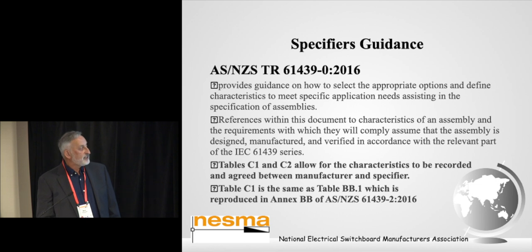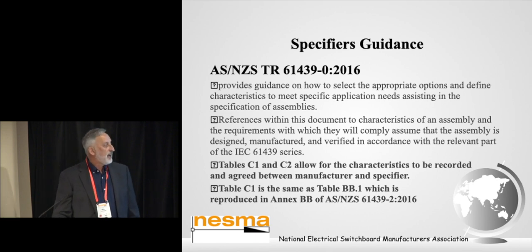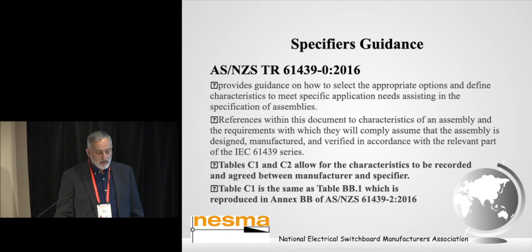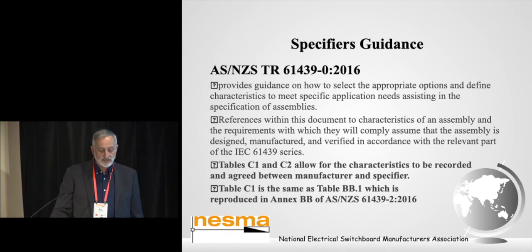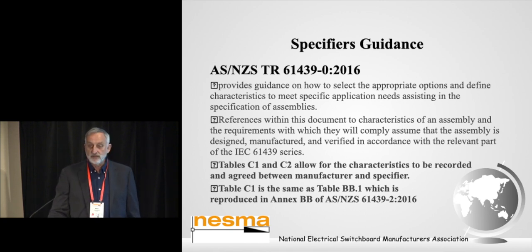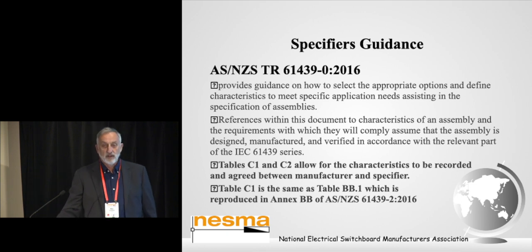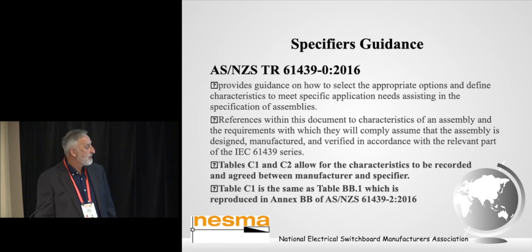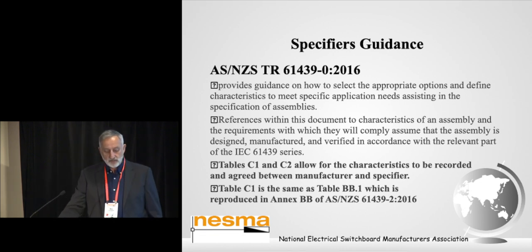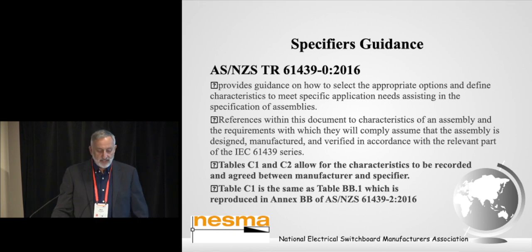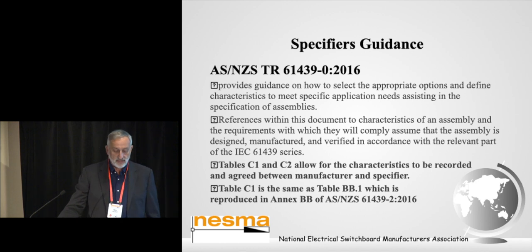So it provides guidance on how to select the appropriate options and define characteristics to meet specific application needs, assisting in specification of assemblies. References within this document to the characteristics of an assembly and the requirements with which they will comply assume that the assembly itself is designed, manufactured and verified in accordance with the appropriate and relevant part of the 61439 series. Now, in this particular document, we have tables C1 and C2, and that enables the characteristics to be recorded and agreed between the manufacturer and the specifier. So a very useful table if you're trying to negotiate an assembly for someone.